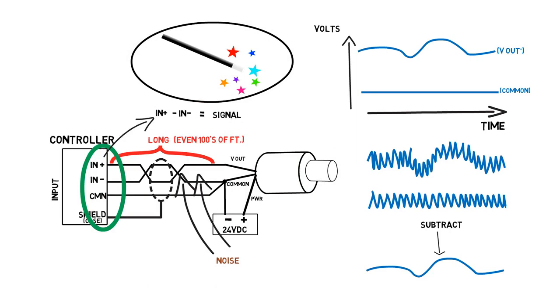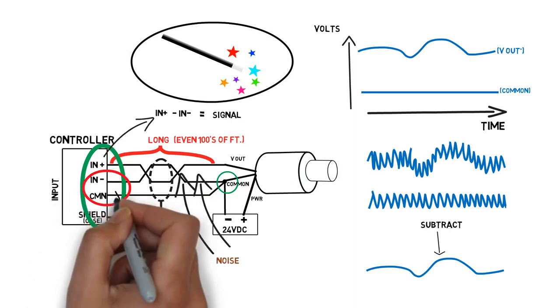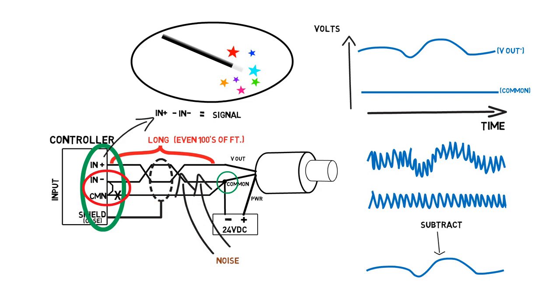In this example, the in minus and common pins are connected at the sensor. If we cheat and connect them at the input, the controller will still receive the signal, but let's see what happens when the wire is subjected to noise.